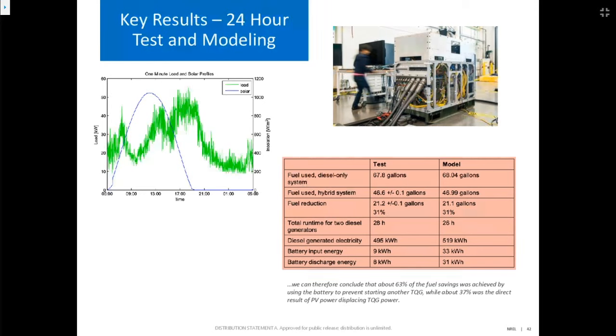But basically, this fuel reduction line here: the diesel-only system used 67.8 gallons in this 24-hour test with this load profile. The cube used 46.6. So we reduced the diesel fuel consumption for that day by 31%, saving roughly 20 gallons of fuel, to do the same job.